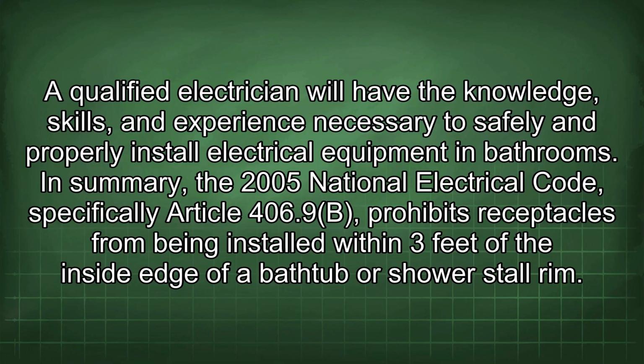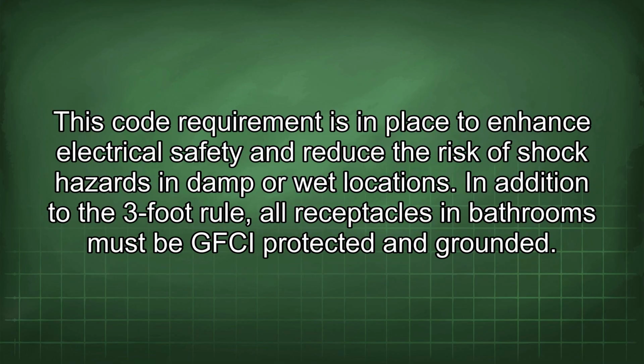In summary, the 2005 National Electrical Code, specifically Article 406.9(B), prohibits receptacles from being installed within 3 feet of the inside edge of a bathtub or shower stall rim. This code requirement is in place to enhance electrical safety and reduce the risk of shock hazards in damp or wet locations. In addition to the 3-foot rule, all receptacles in bathrooms must be GFCI protected and grounded.